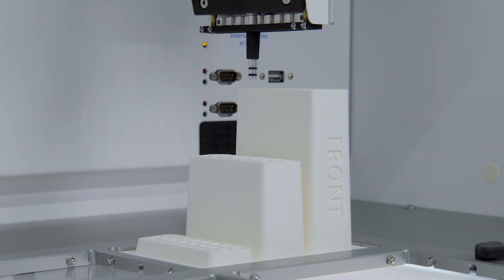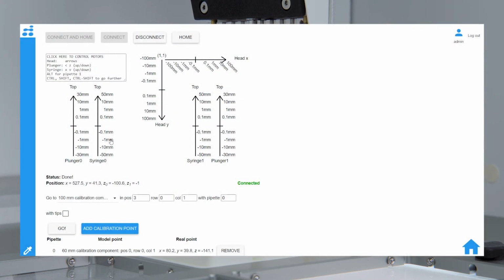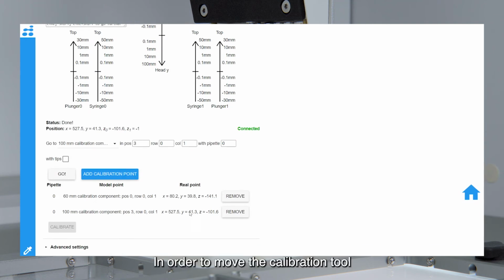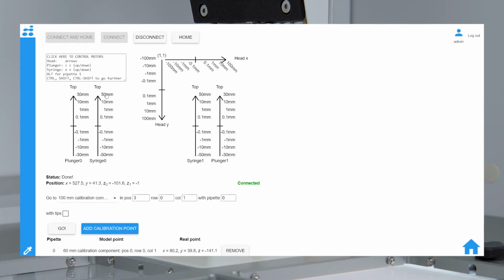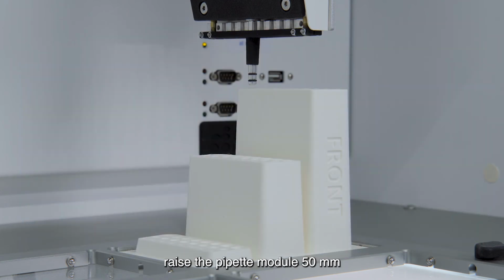Like before, you adjust the syringe down until it is aligned with the surface of the target and not into the well. Once it is aligned, use a piece of paper between the well and the tip cone to make sure that it's not touching the well. Like before, when you are happy with your alignment, add calibration point. In order to be able to move the calibration tool, raise the pipette module 50 millimeter.